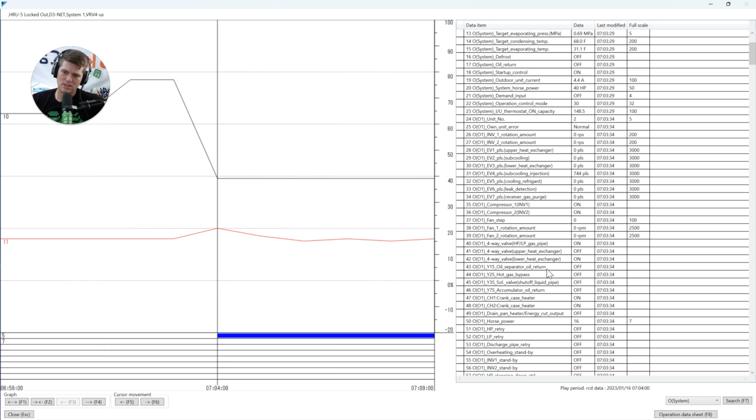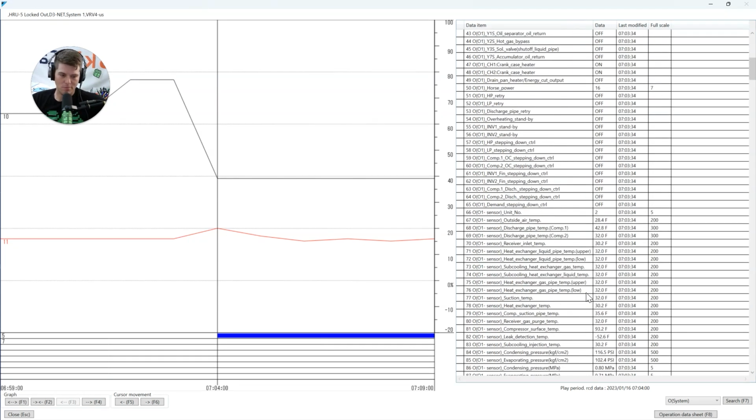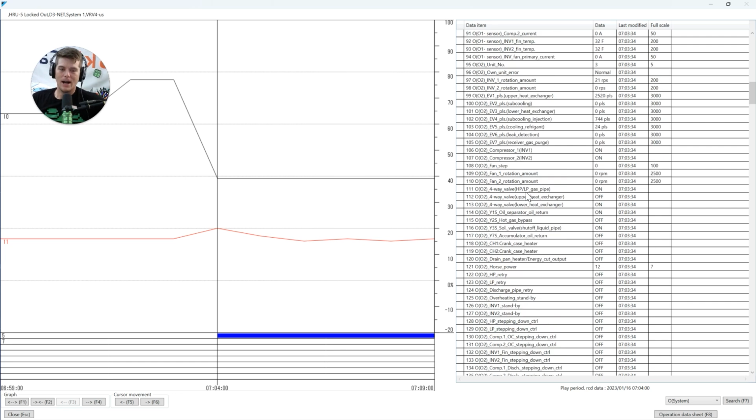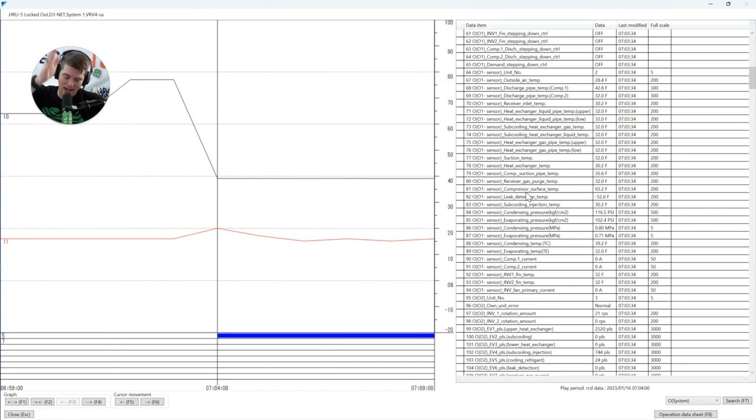So if you know specifically what you want to see a correlation between, typically suction pressure correlates to compressor speeds, but maybe I also want to correlate those two things with indoor valve pulses. I can't populate all those valve pulses here, but if I go to detailed view, I can see all my valve pulses for every indoor unit at the same time. And I can see, well, wait a minute, 50% of them shut. And then my compressor speed went way down, right? And my suction pressure dropped or skyrocketed or did whatever. It's helping you connect those dots between everything at one time.